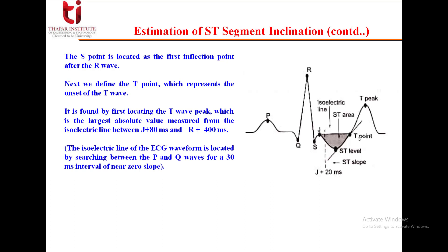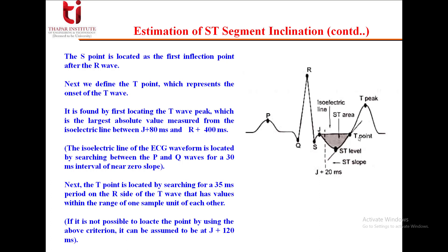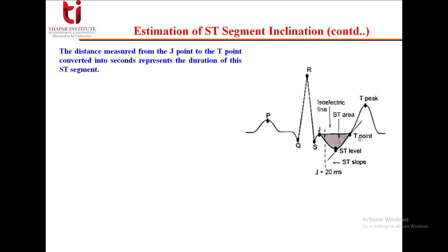The isoelectric line of the ECG waveform is located by searching between the P and Q waves for a 30 ms interval of near zero slope. Next, the T point is located by searching for a 35 ms period on the R side of the T wave that has values within the range of one sample unit of each other. If it is not possible to locate the point using the above criteria, then it can be assumed to be at J plus 120 ms.